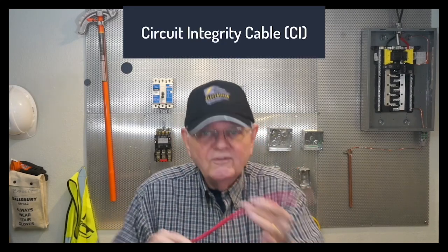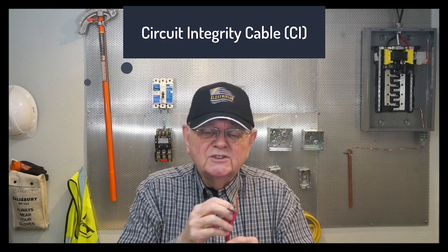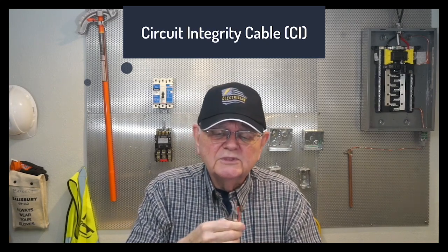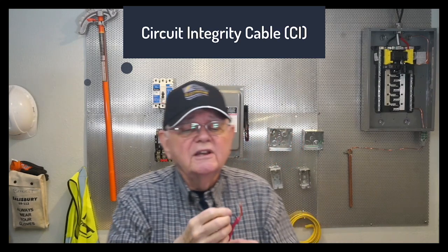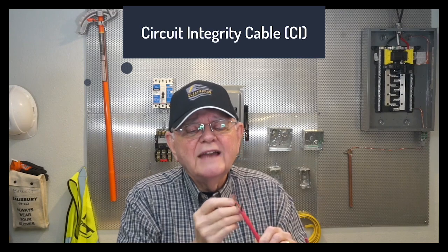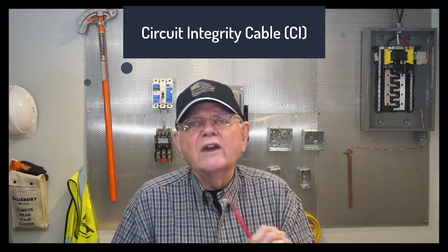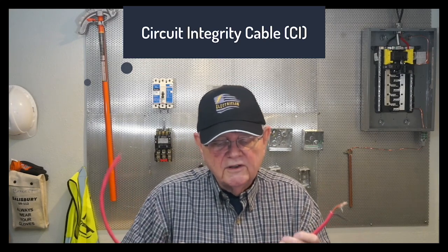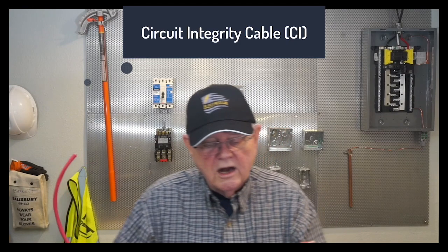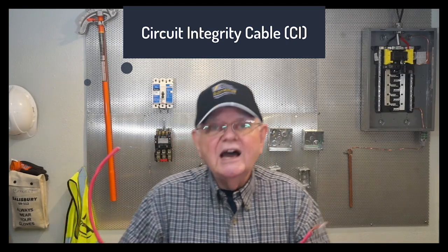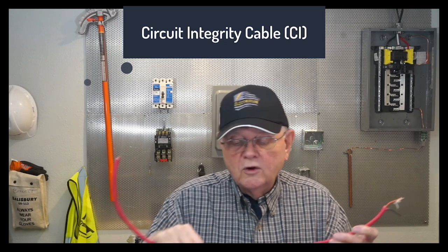Here's another cable you'll find in those 44 definitions. This is some circuit integrity cable. If I look at this, it's got the jacket on the outside. That's pretty stiff, pretty hard. Then I've got some insulation, but when I take off the insulation, there's some glass material, like fiberglass material, wrapped around the conductor. If I take a look at the ratings on this cable, 16 gauge FPLR-CI, the CI tells me it is circuit integrity cable according to the definition, and it is 2-hour fire resistive cable. And then it goes on from there. So anyway, circuit integrity cable, 2-hour fire resistance.